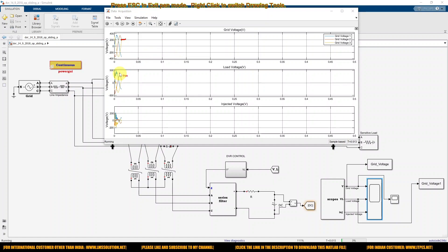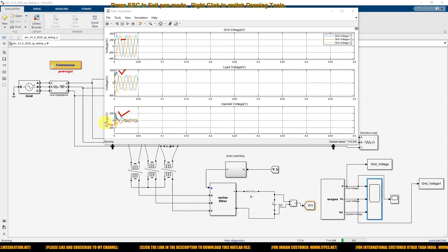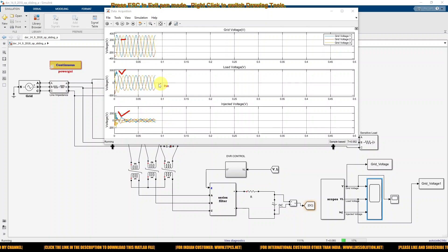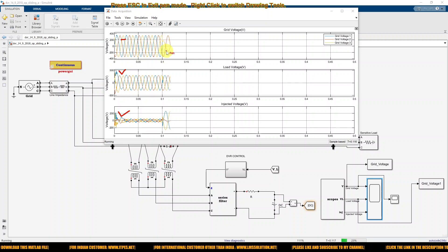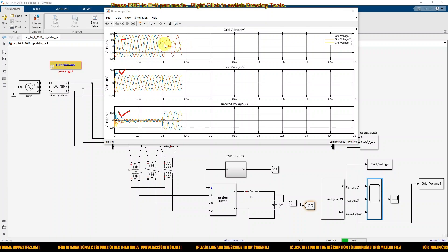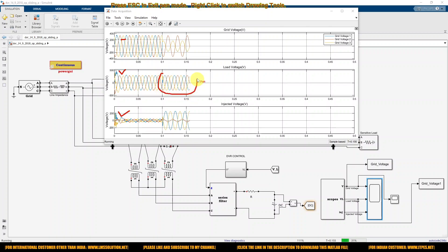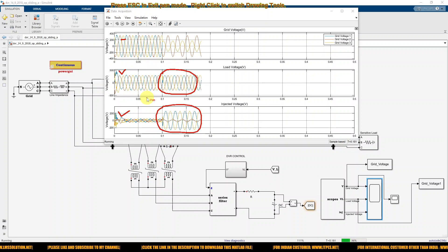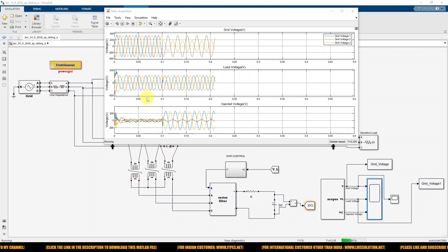Now running the simulation — this is the grid voltage, this is the load voltage, and this is the injected voltage in the sensitive load area. After 0.1 seconds the fault occurs and we can see variation in the grid voltage. A voltage sag appears on two phases, but the load voltage is maintained at one per unit because the DVR is injecting voltage to keep the load voltage constant from 0.1 to 0.3 seconds.